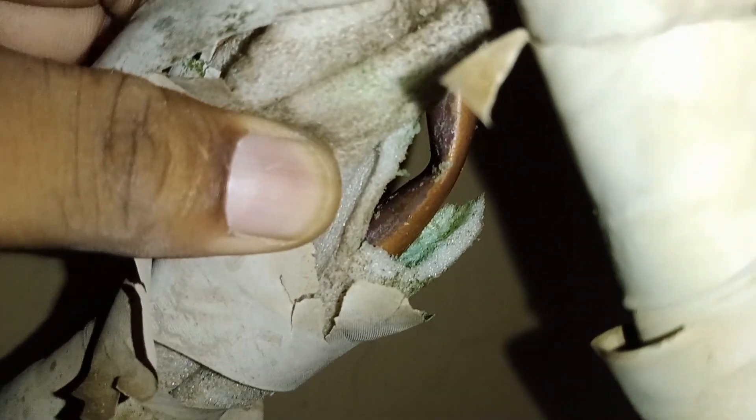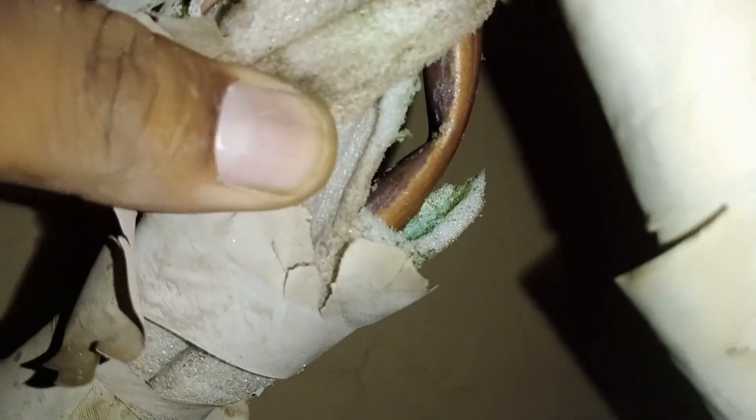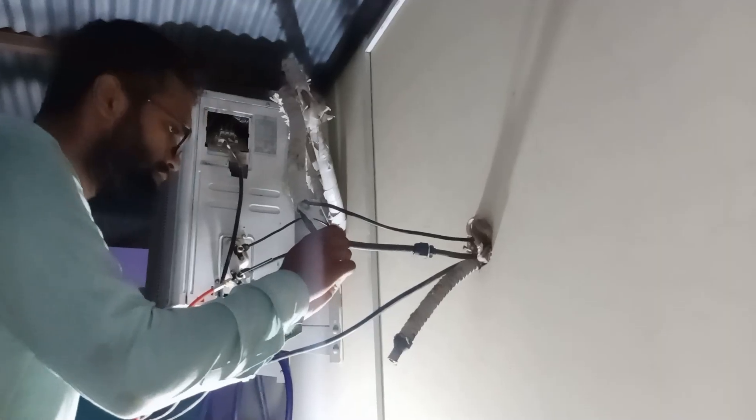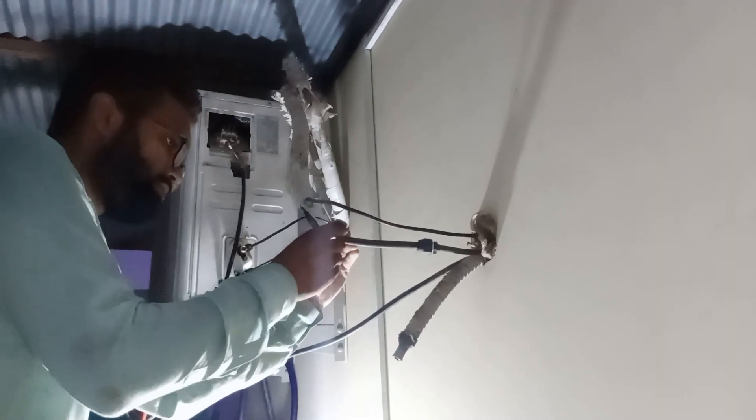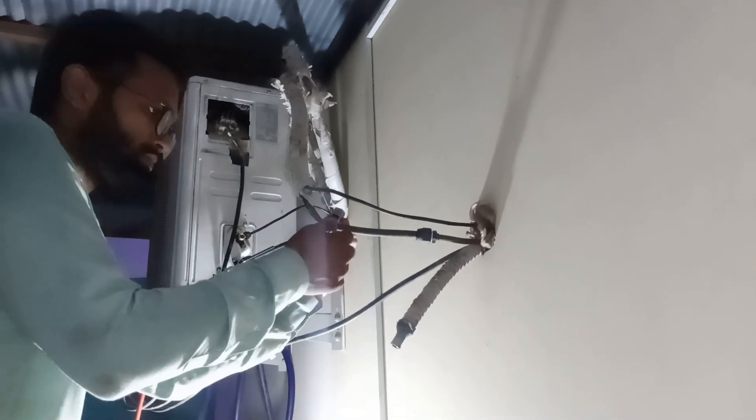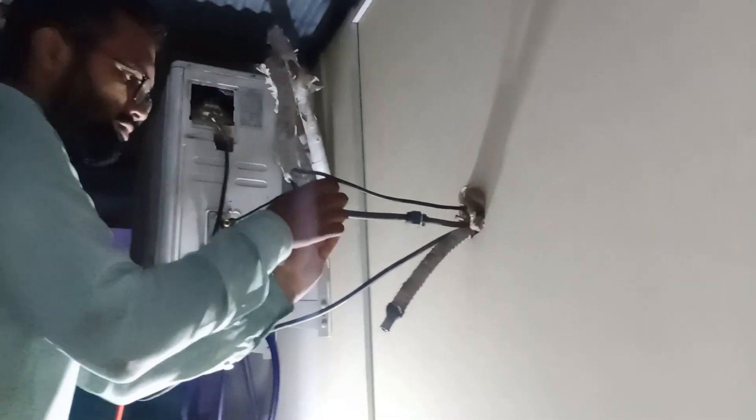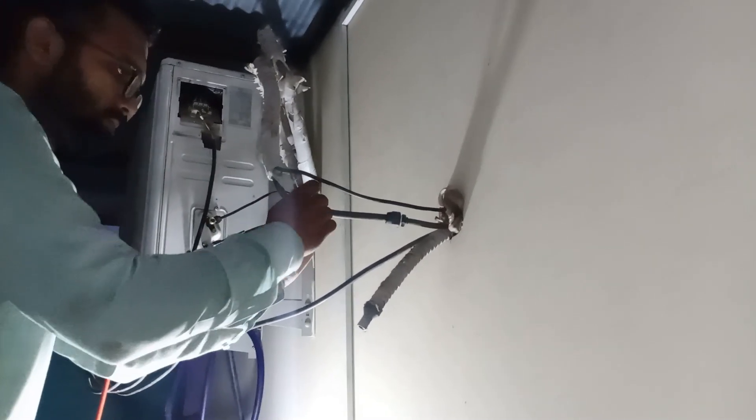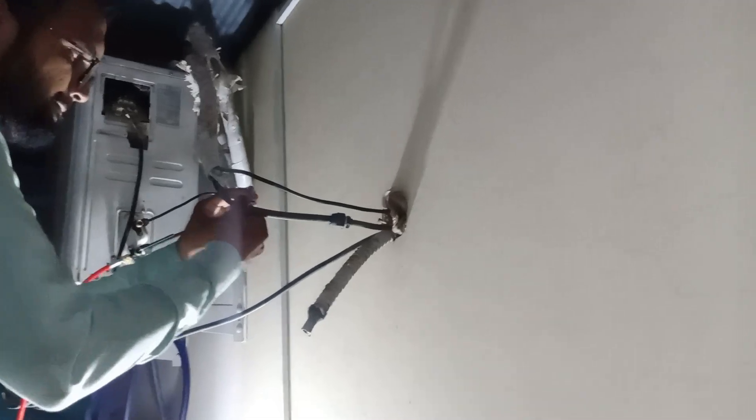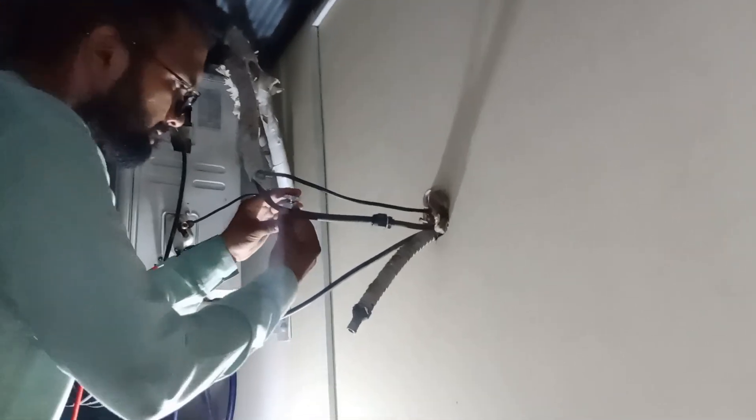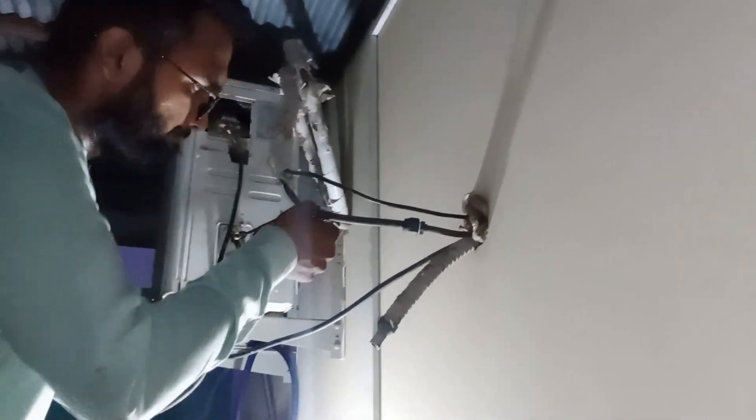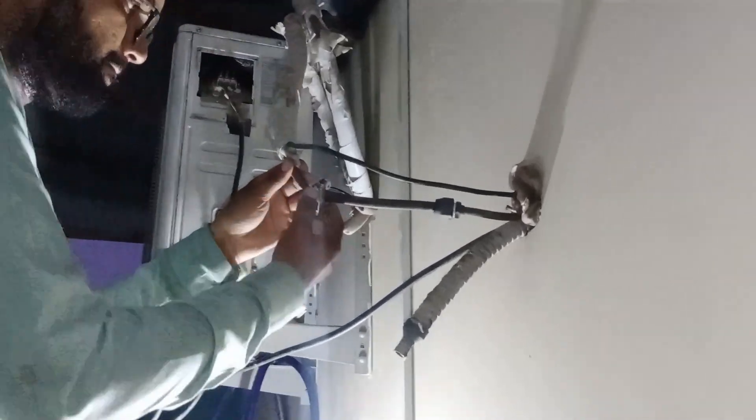Although the rest of the pipe seemed fine, I inspected it more closely by pressing and feeling through the insulation. It turned out that the pipe was bent to the extent that only 10 to 20% of the gas could pass through. This was a significant blockage, as the pipe was approximately 70% bent at that point. Solution: Since the pipe was too rigid to straighten without causing damage, the solution was to cut the bent section and replace it with new joints. This ensured that the pipes were completely fresh and free from blockages.